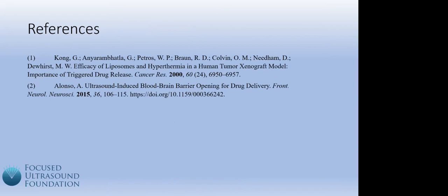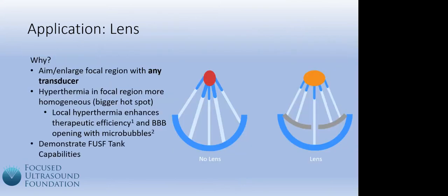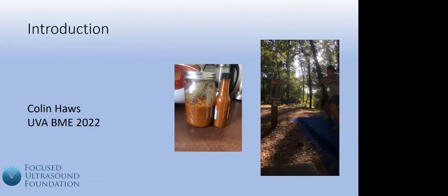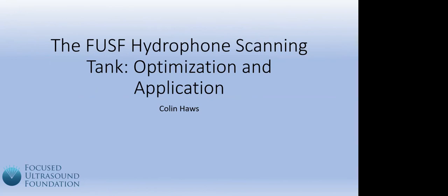Hi, I put a question in the chat basically asking how much time it takes to scan one layer? So if I heard correctly, for a 2D scan. Yes, for one layer, it depends on your resolution. Most of these images have been done at a 250 micron resolution. With that step size, a scan takes about 20 minutes, which is a little bit longer than about 15 minutes for the commercial design. But a lot of that includes integrated pauses, which are required to acquire your signal in a safe and non-noisy method.